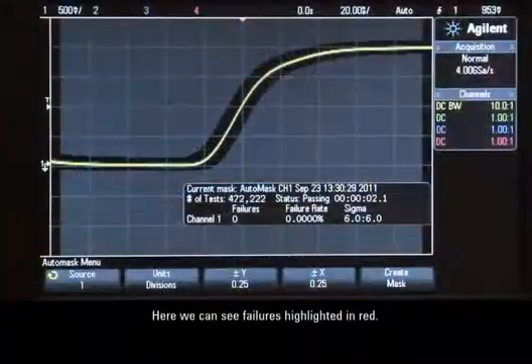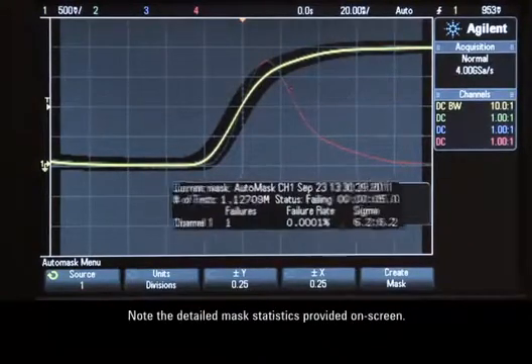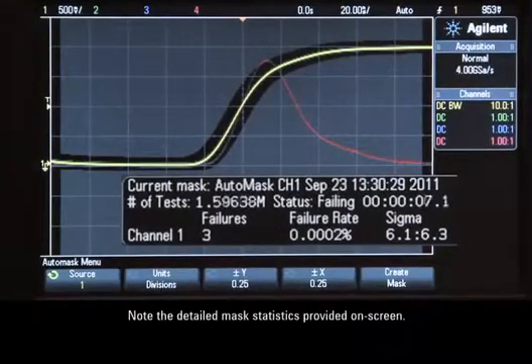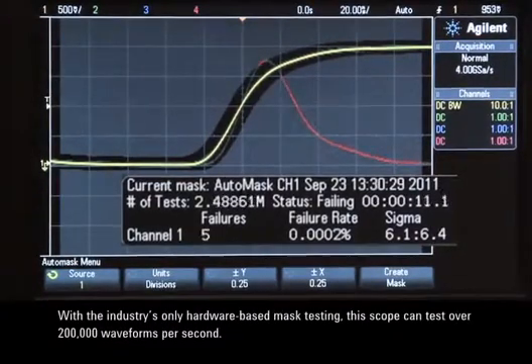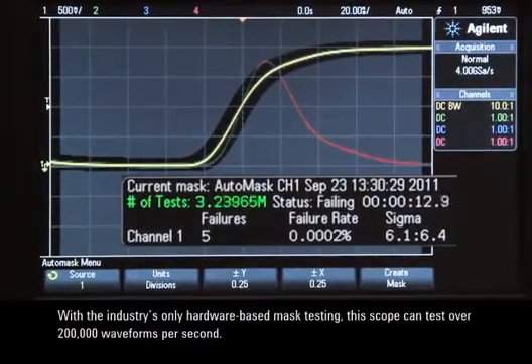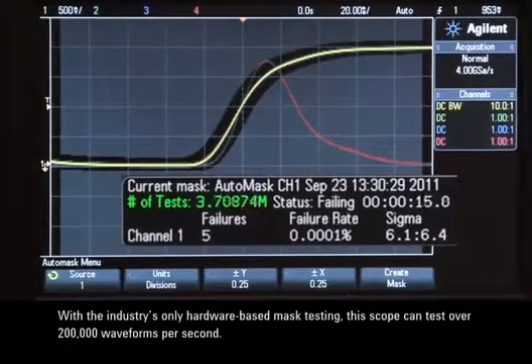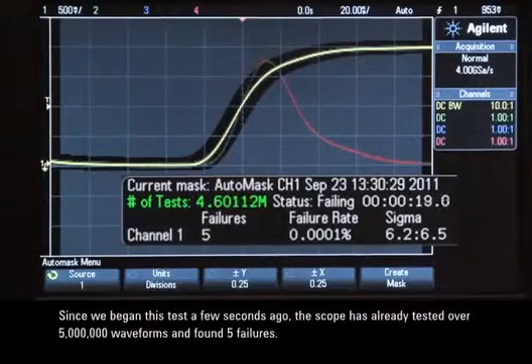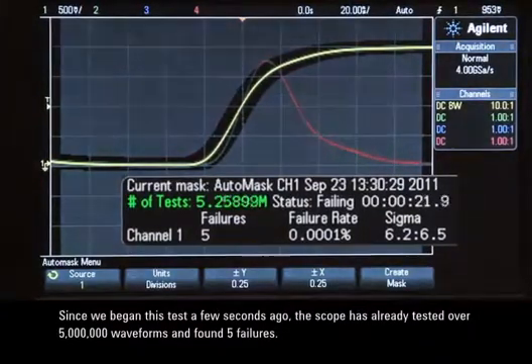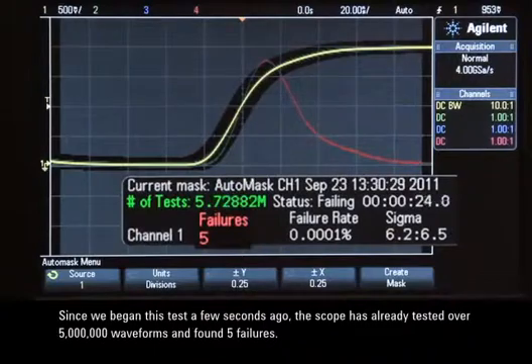Here we see failures highlighted in red. Note the detailed mask statistics provided on screen. With the industry's only hardware-based mask testing, this scope can test over 200,000 waveforms per second. Since we began this test a few seconds ago, the scope has already tested over five million waveforms and found five failures.